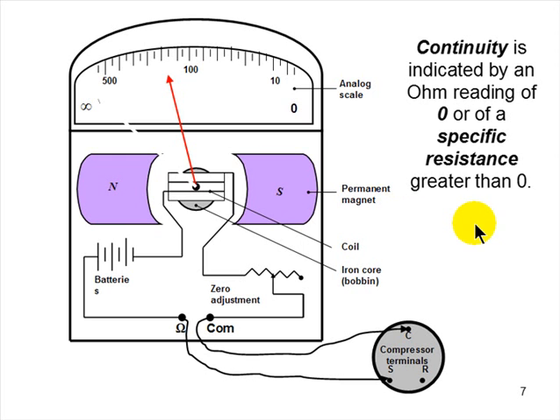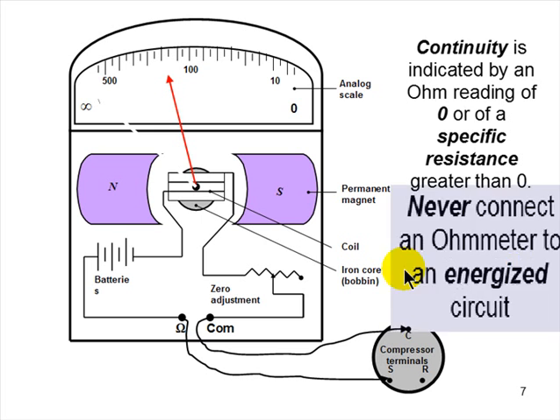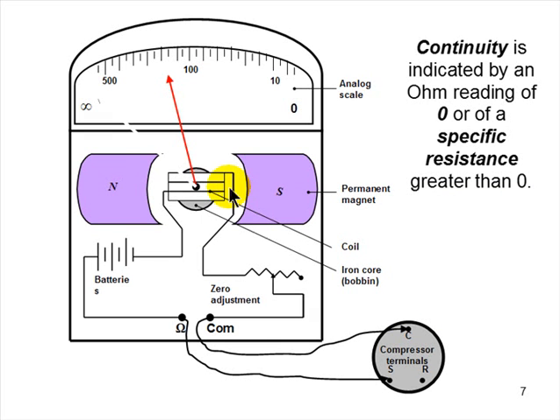Continuity is defined technically as an ohm reading of 0 or a specific resistance. Either a dead short shows continuity, or some specific value that's not infinite. That is resistance. That is continuity. If you lack continuity, you're going to have infinite resistance, infinite ohms, if you will. Never connect an ohm meter to an energized circuit, for the reasons I showed you. This internal circuit here is extremely light, extremely fine wire, thinner than your hair.